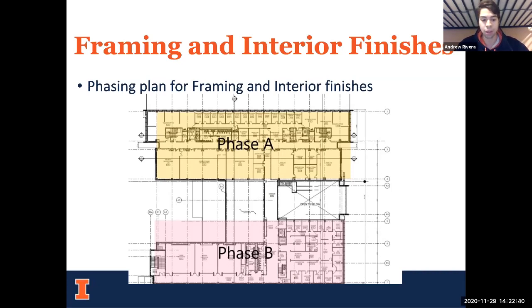Once major mechanical ducts and electrical conduit are in place, it's possible to frame partitions on the associated level. After studs and partitions are installed, ceiling grids are roughed in and installed, and lighting and equipment needing to be routed above the drop ceiling are placed before the ceiling system is installed. Electrical wiring is then fed through the partitions to the roughed-in outlets in the walls.